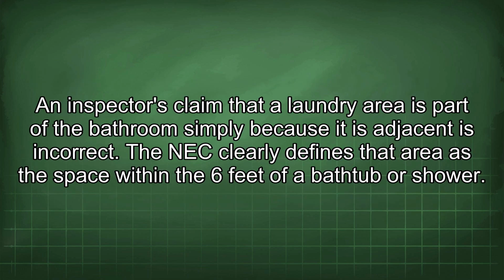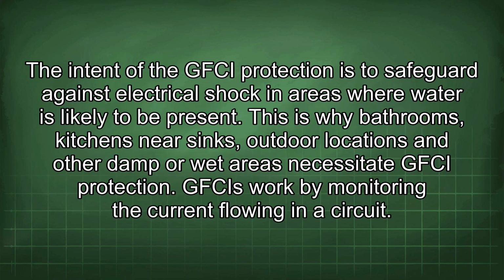An inspector's claim that a laundry area is part of the bathroom simply because it is adjacent is incorrect. The NEC clearly defines that area as the space within the 6 feet of a bathtub or shower. The intent of the GFCI protection is to safeguard against electrical shock in areas where water is likely to be present. This is why bathrooms, kitchens near sinks, outdoor locations, and other damp or wet areas necessitate GFCI protection.